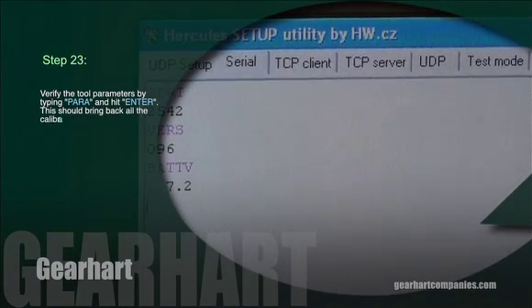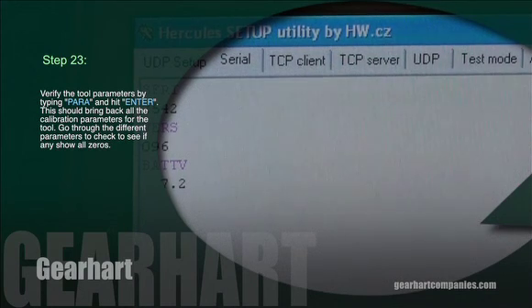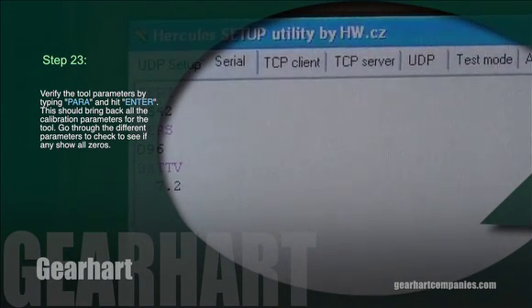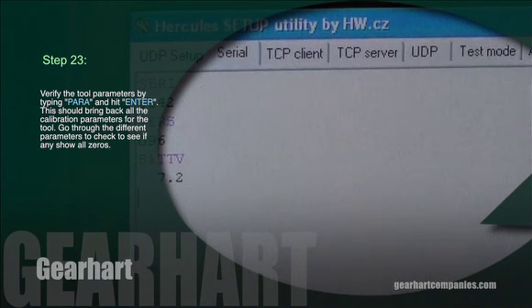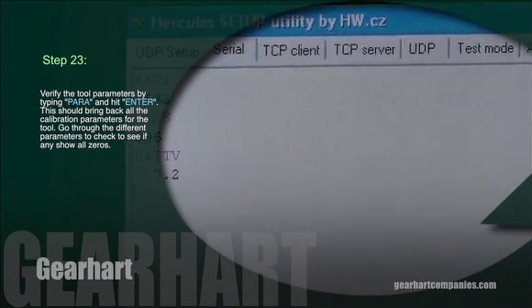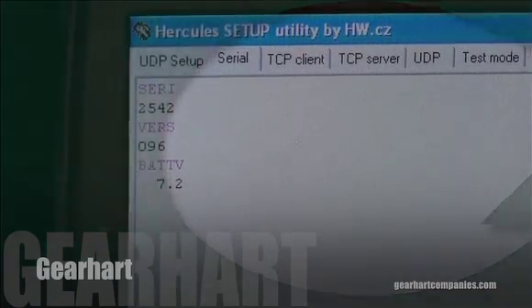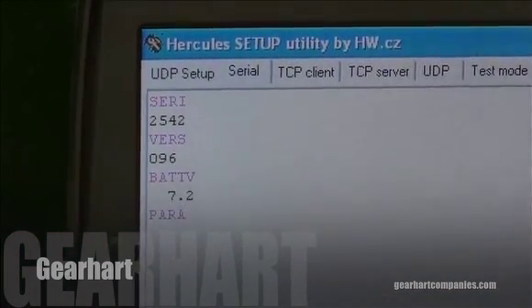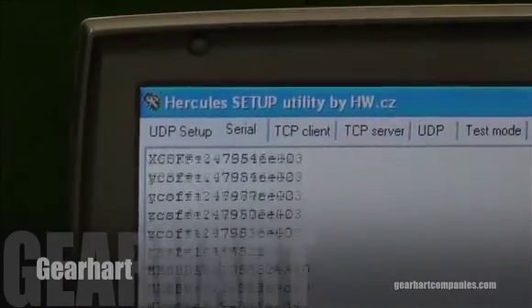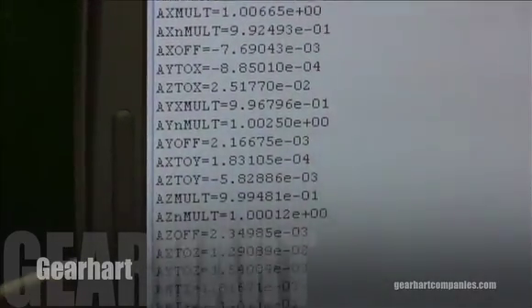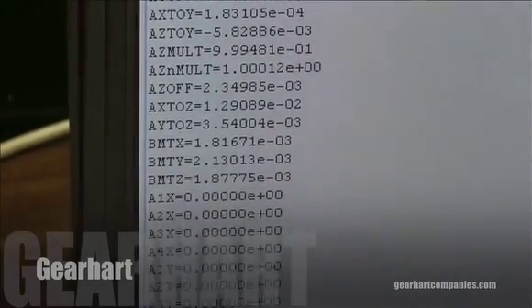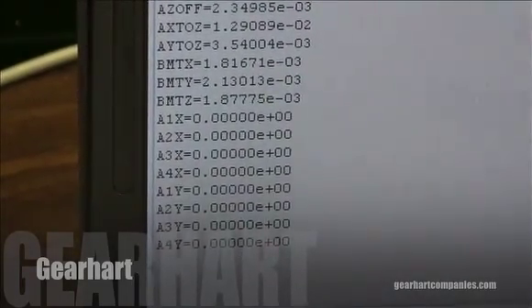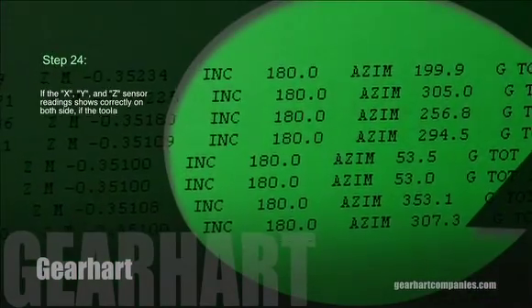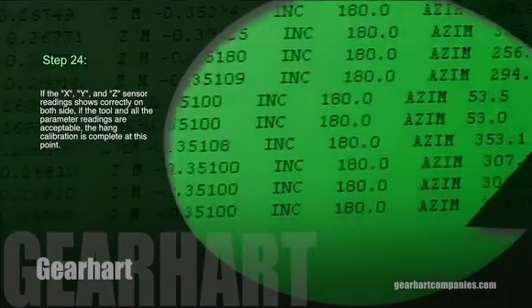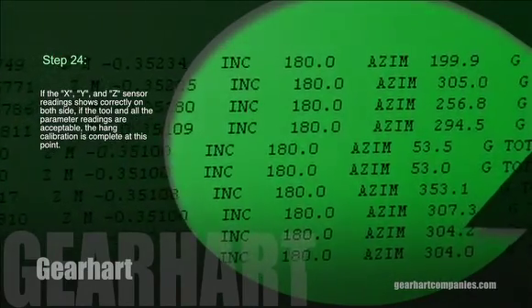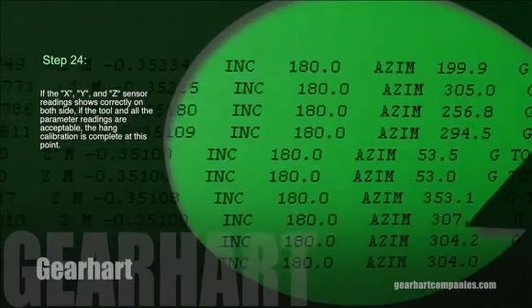Step 23. Verify the tool parameters by typing PARA and hit enter. This should bring back all the calibration parameters for the tool. Go through the different parameters to check to see if any show all zeros. Step 24. If the X, Y, and Z sensor readings show correctly on both sides, and all the parameter readings are acceptable, the hang calibration is complete at this point.